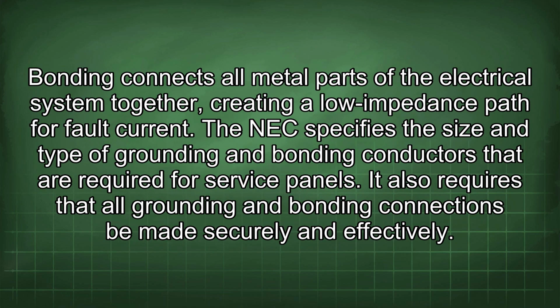Bonding connects all metal parts of the electrical system together, creating a low impedance path for fault current. The NEC specifies the size and type of grounding and bonding conductors that are required for service panels. It also requires that all grounding and bonding connections be made securely and effectively.